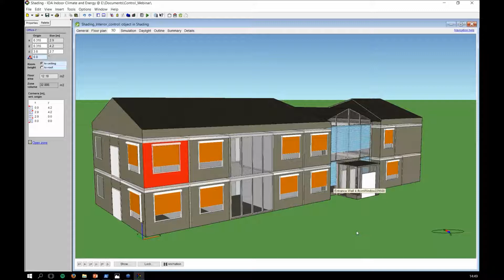Okay, so Samer has a question. You see that? Can you decide the location of the sensor in the room? Yes. If you go to system parameters, you see here the method of measurement of daylight level. When we went to the zone sensor and selected daylight signal, this is actually measured at first occupant. So it's either an average over floor area or a point measurement at first occupant. Since it is a point measurement at first occupant, wherever you move your occupant, that measurement will move.